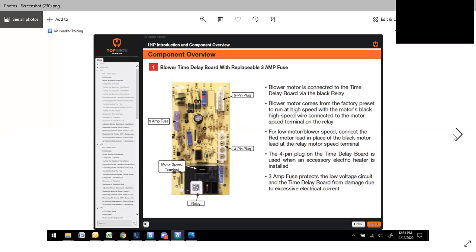The blower motor is connected to the Time Delay Board via the black relay right here, motor terminals right here. The blower motor comes from the factory preset to run at high speed, with the motor's black high-speed wire connected to the motor speed terminal. For low blower speed, connect the red motor lead in place of the black. The 4-pin plug here is used only if you're using auxiliary heat. If you're doing just a cooling only air handler, this will not be used. There again, it has a 3-amp fuse.